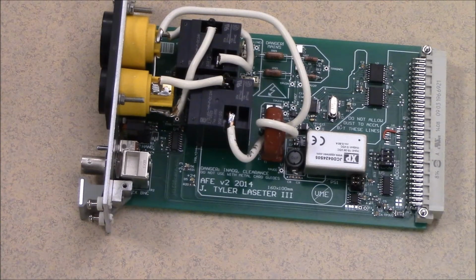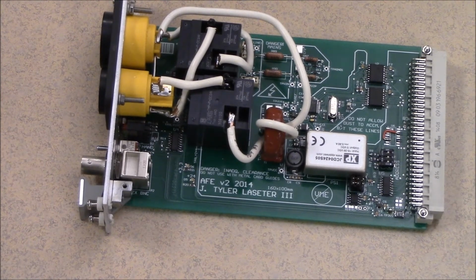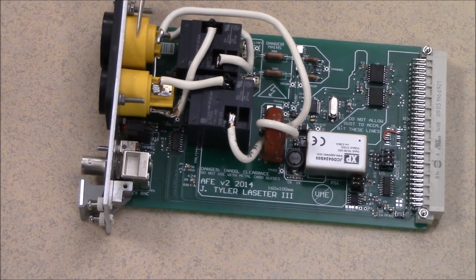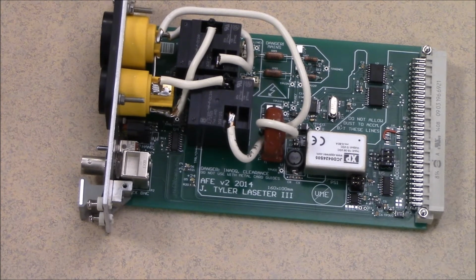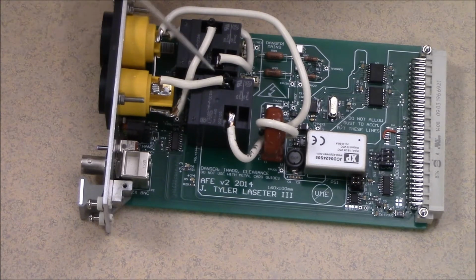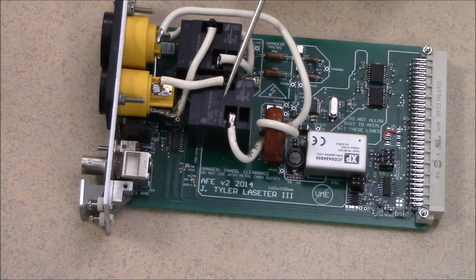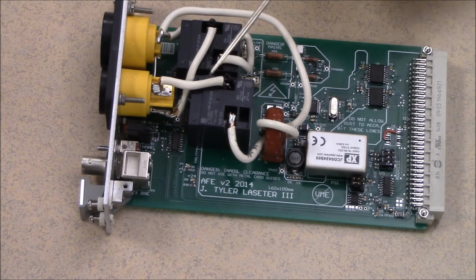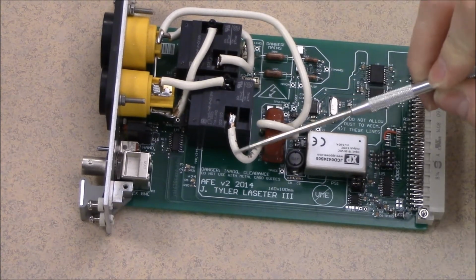Here we have the analog front end module. This module is the heart of our measurements that are taken. So we have some Neutrik power connectors, one male, one female. Power enters here and is switched by these 2 relays, which are each 30 amp relays, which is outside of our specification of measurement of 20 amps, to try and reduce inaccuracies caused by drop across those relays and to improve reliability.